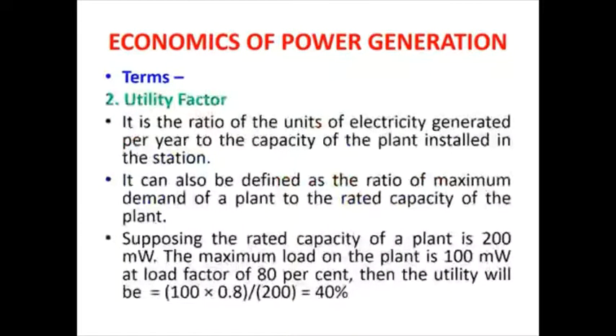Second, utility factor. It is the ratio of units of electricity generated per year to the capacity of the plant installed in the station. It is also defined as the ratio of maximum demand of a plant to the rated capacity of the plant. Here again we will have one example. Suppose the rated capacity of a plant is 200 megawatt. So this is the maximum capacity of a particular plant, 200 megawatt. Maximum load on the plant is 100 megawatt at a load factor of 80%.